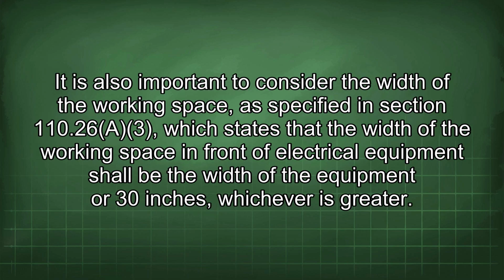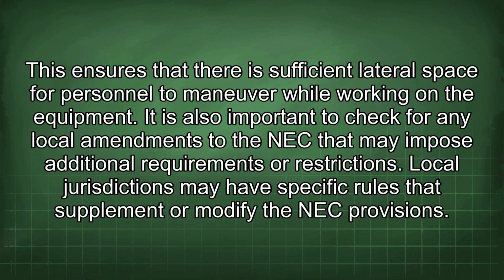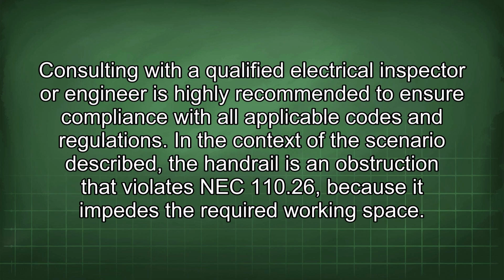It is also important to consider the width of the working space, as specified in Section 110.26(a)(2), which states that the width of the working space in front of electrical equipment shall be the width of the equipment or 30 inches, whichever is greater. This ensures that there is sufficient lateral space for personnel to maneuver while working on the equipment. It is also important to check for any local amendments to the NEC that may impose additional requirements or restrictions. Local jurisdictions may have specific rules that supplement or modify the NEC provisions. Consulting with a qualified electrical inspector or engineer is highly recommended to ensure compliance with all applicable codes and regulations.